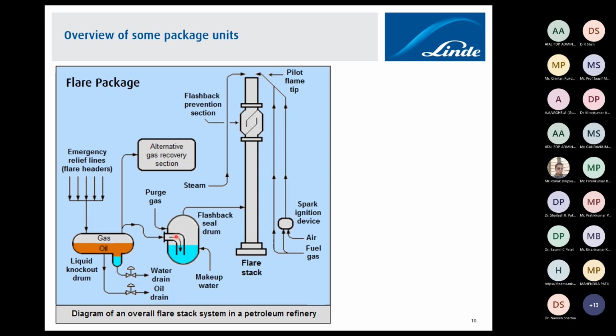Before we feed it into the flare stack, there is a water seal, because if anything happens, there should not be any burn back coming back to the seal drum and traveling back into the industry, where hydrocarbon is easily available and can create fire. So you will always find a water seal device. All the gases go via the liquid, and only then do the gases go to the stack. Similarly, another safety device you will find on the stack is the flashback prevention section, that is, a flashback seal. Whenever there is firing back because of improper stoichiometry, it won't come back and will be prevented over here. So this is the kind of arrangement available.